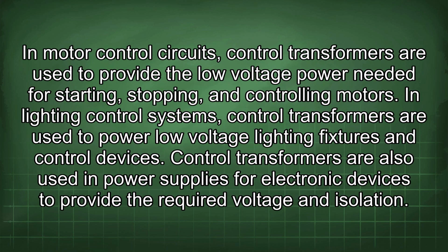In motor control circuits, control transformers are used to provide the low voltage power needed for starting, stopping, and controlling motors. In lighting control systems, control transformers are used to power low voltage lighting fixtures and control devices. Control transformers are also used in power supplies for electronic devices to provide the required voltage and isolation.